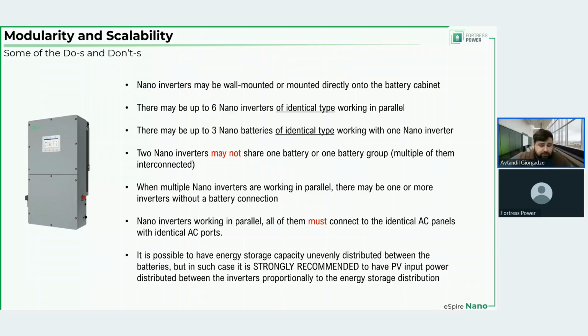If you have uneven distribution of batteries between the inverters, it is strongly recommended that PV is distributed proportionally to the energy storage distribution, so it's easier for the inverters to keep the batteries balanced at the same SOC level or around the same SOC level. Let's quickly visualize these concepts.